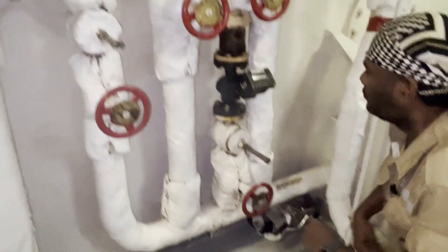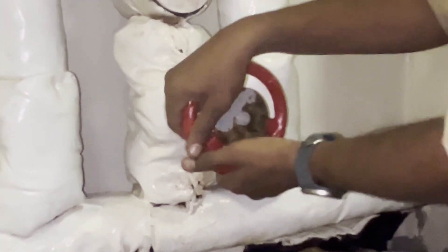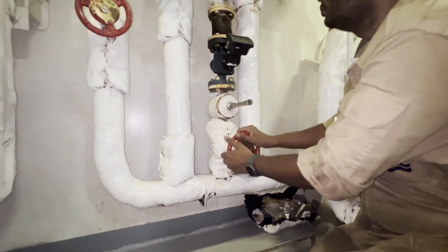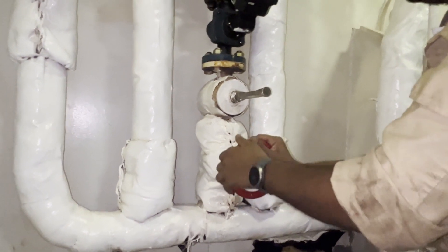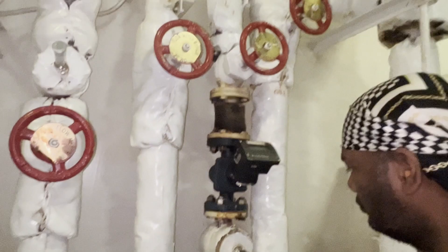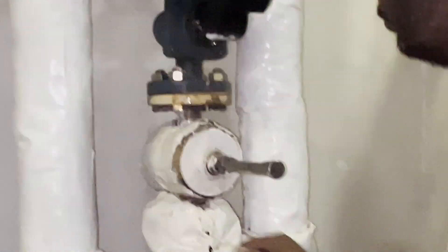You can see the bypass valve is completely opened. Do not use any kind of wheel spanner to tighten the fuel oil line valves unless it is very necessary, because if you use a wheel spanner you are going to damage the valves. Close the inlet valve of the flow meter first, and once that is done, close the outlet valve.